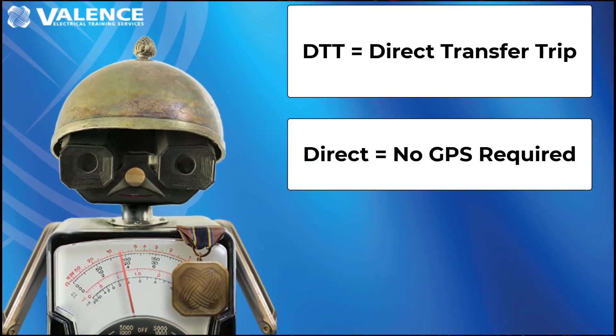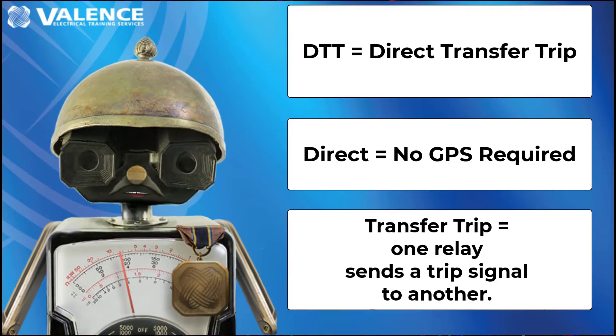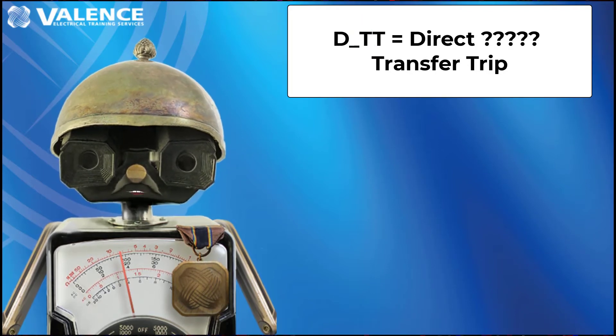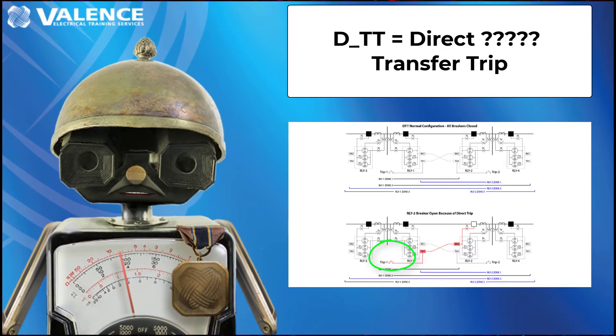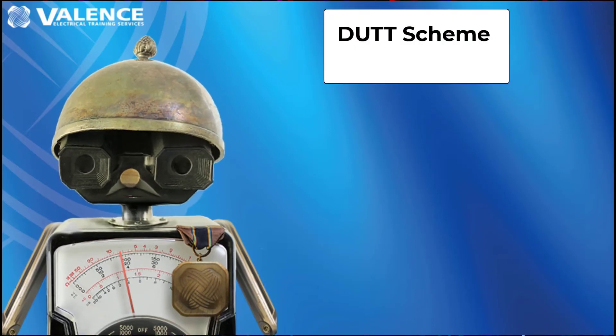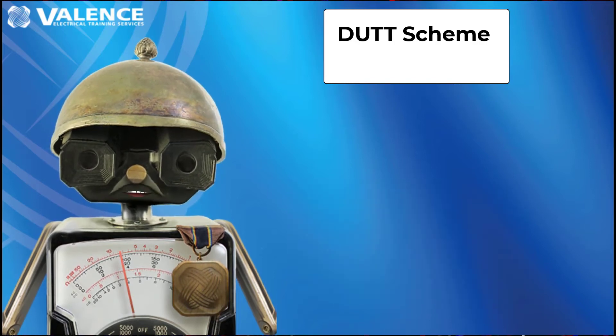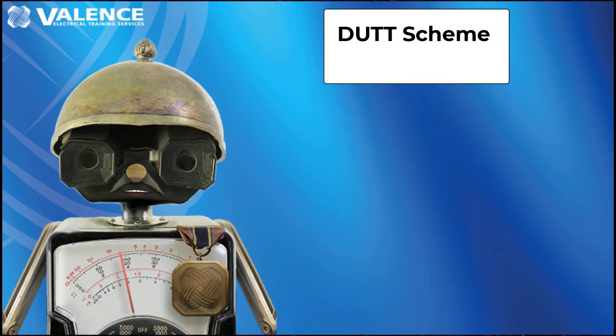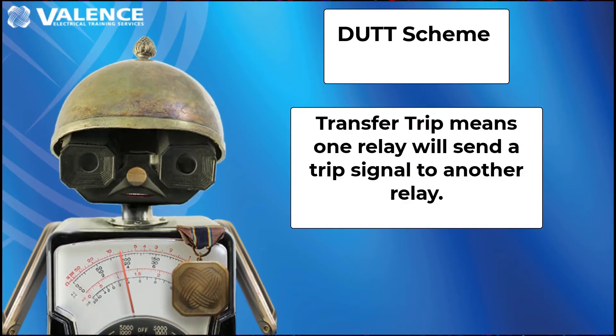Direct tells you that you don't need any fancy GPS or IRIG connected equipment to test this scheme. Transfer trip tells you that one relay will send a trip signal to the other. There could be another letter telling you which zone to apply, but it's missing from this acronym, so that means there will be an external signal initiating the transfer trip — like a breaker failure relay or a 52B signal — that will isolate both sides of a line if one breaker operates. For a DUTT scheme, direct means no fancy time-synced test equipment is required on both ends. The U stands for underreaching, so one relay will need to measure a Zone 1 signal to send a trip to the other side, and a relay test set will be required.